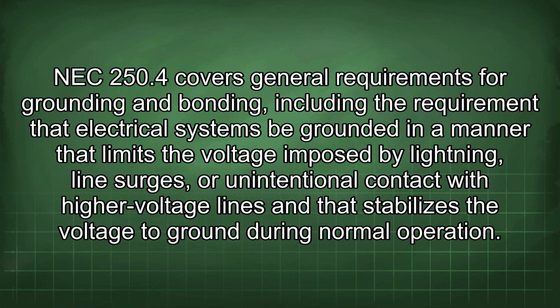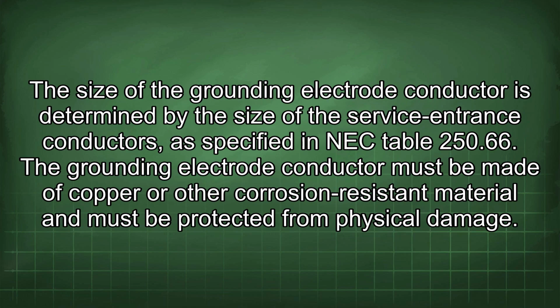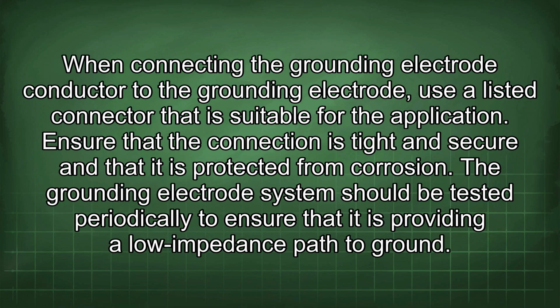NEC 250.4 covers general requirements for grounding and bonding, including the requirement that electrical systems be grounded in a manner that limits the voltage imposed by lightning, line surges, or unintentional contact with higher voltage lines, and that stabilizes the voltage to ground during normal operation. The size of the grounding electrode conductor is determined by the size of the service entrance conductors, as specified in NEC Table 250.66. The grounding electrode conductor must be made of copper or other corrosion-resistant material and must be protected from physical damage. When connecting the grounding electrode conductor to the grounding electrode, use a listed connector that is suitable for the application.